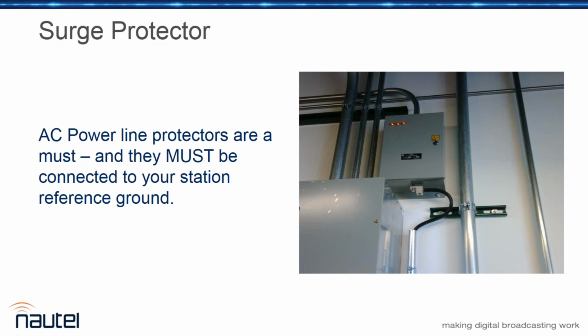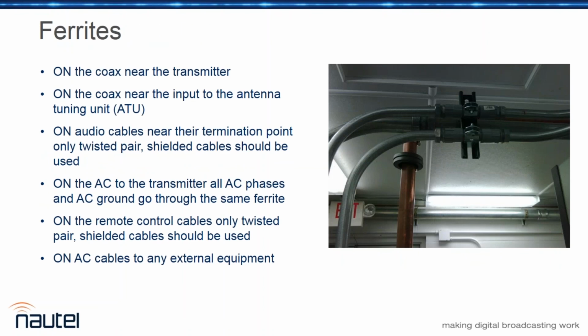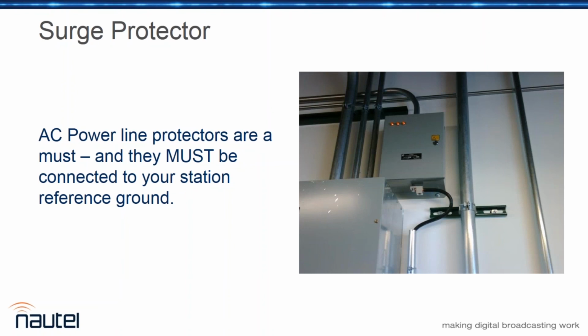So would you leave it open the whole way, or is it okay to have a stub like you have there, as long as it's not connected at both ends like a shield? For the conduit, I would prefer to have a non-metallic conduit, or to have the ground wire actually physically bonded to the conduit. Make the conduit part of the ground wire. Okay. Depending on where you are, what building you're in, what city you're in, different codes will require different things. Sometimes you don't have the option. Sometimes you have to run. And this particular surge box is in Chicago, and steel conduit's a requirement.